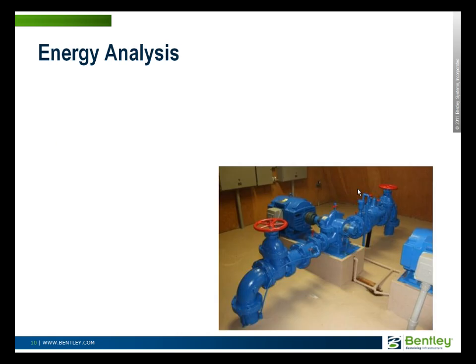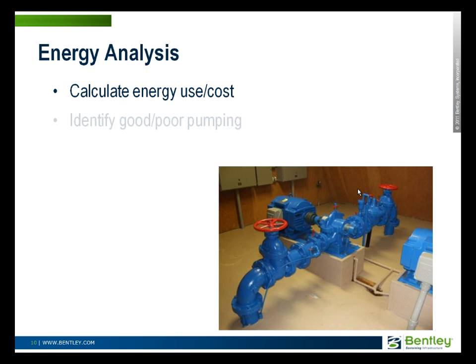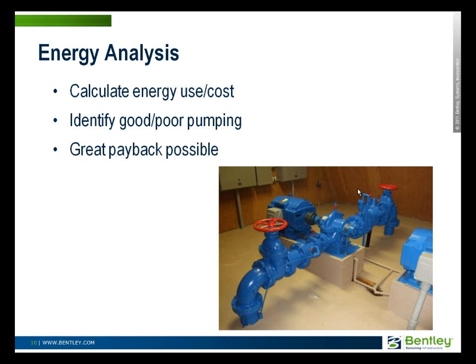Energy analysis is another important use of water distribution system modeling. The models calculate the amount of energy used and the cost of that energy, and there are usually some surprises when you do this. You can identify places where you're not pumping very efficiently, or where you're doing a very good job. In places where you're not pumping efficiently, the model can show you what pumps ought to be replaced or how pump operation should be modified. There's a lot of payback in running the model, finding these places where the system is not running efficiently, and modifying the operations or pumping equipment to make the system operate more efficiently.